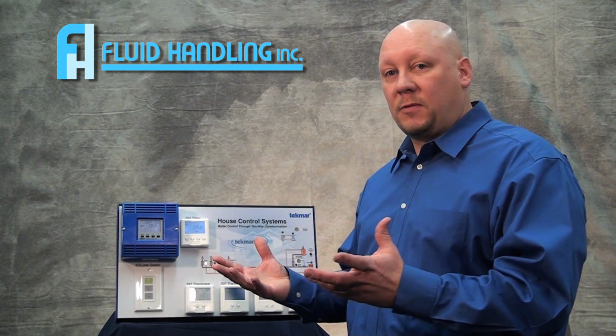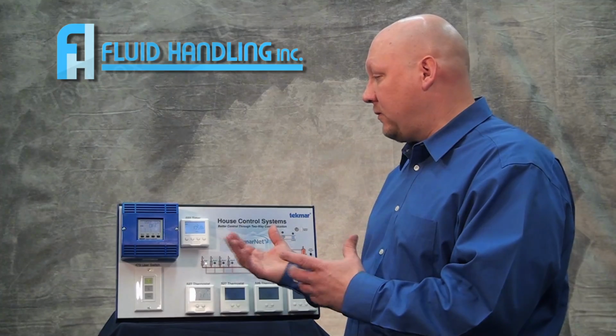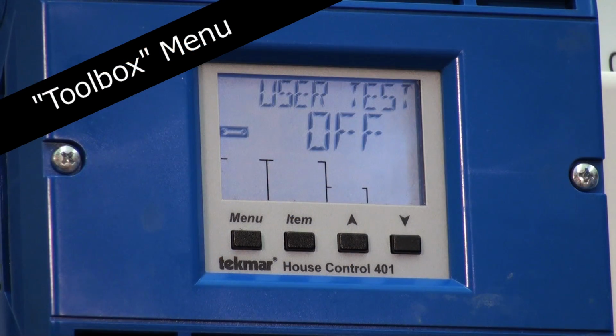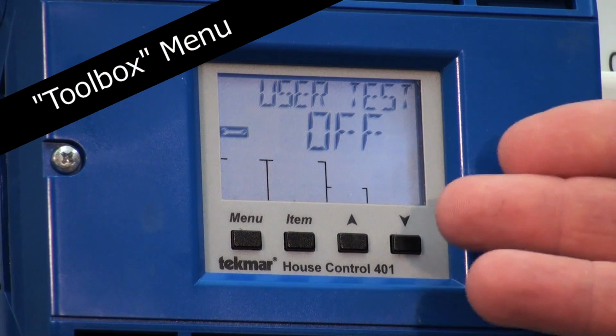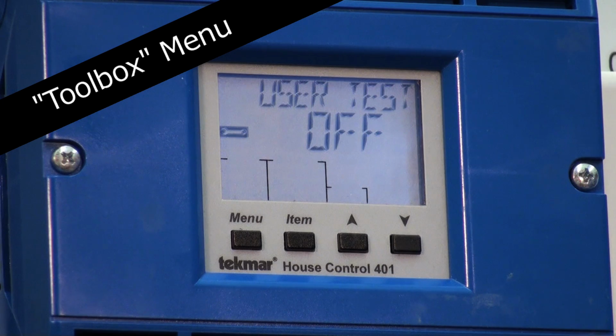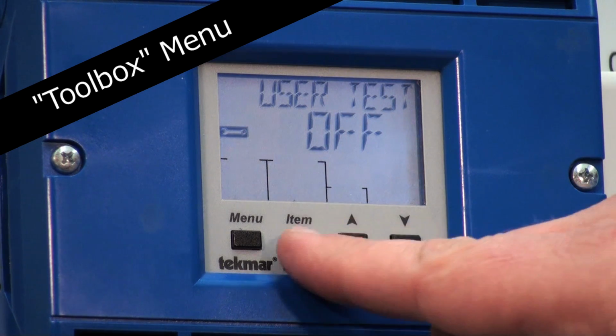If you are starting up the system, say you've had temporary heat in there in the wintertime, so it's hard to get a good run time to get the boiler to 100% fire, you can go in here, turn the user test to on. The control will go through each individual relay and turn them on and off a few seconds at a time to make sure that everything is functioning.